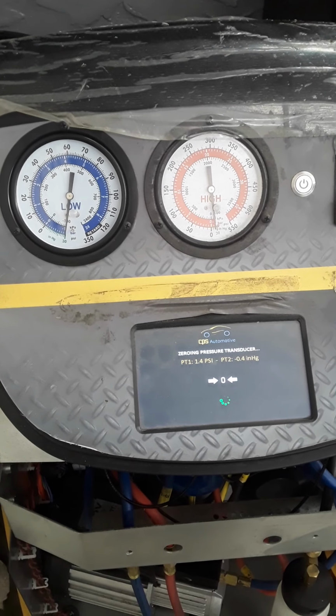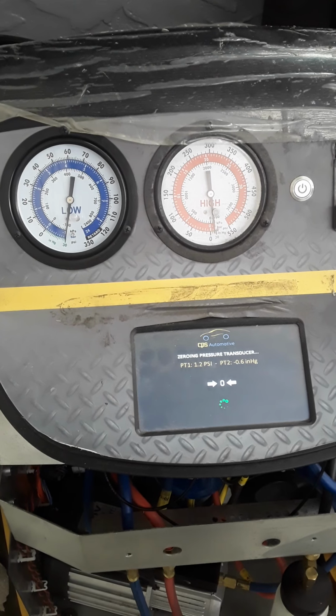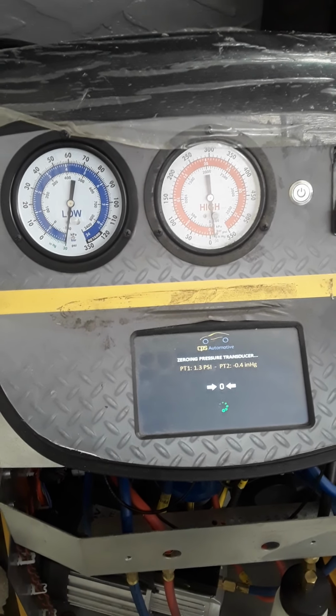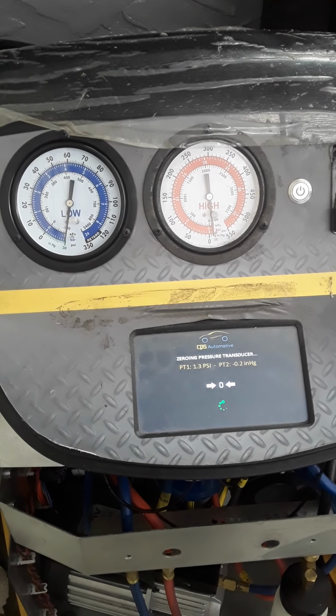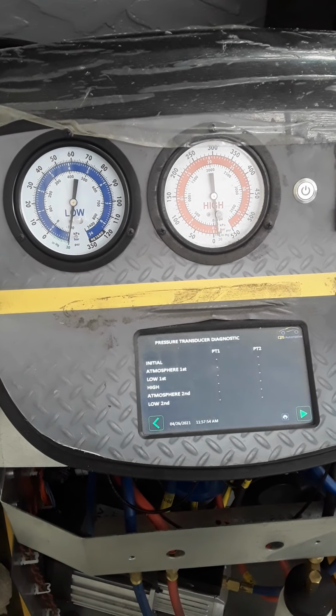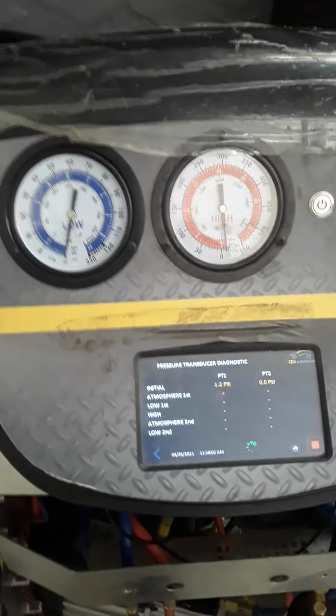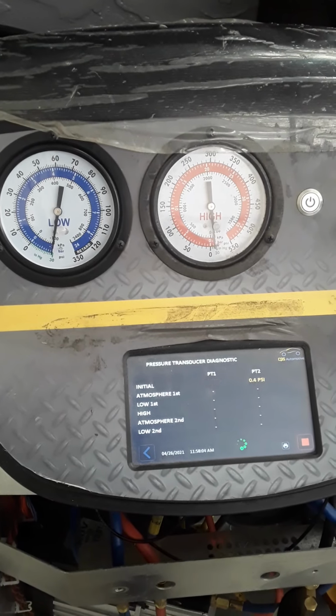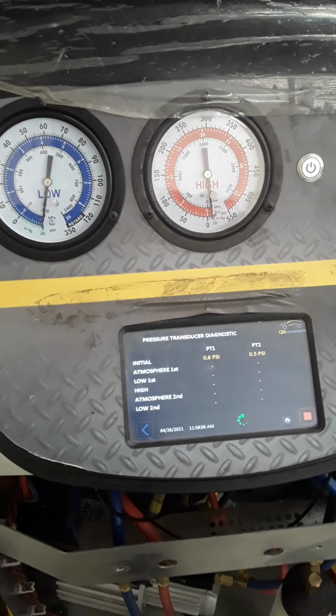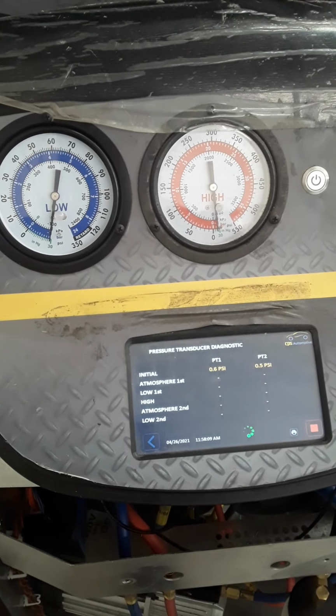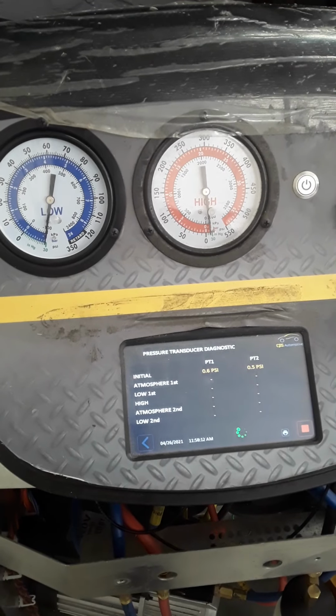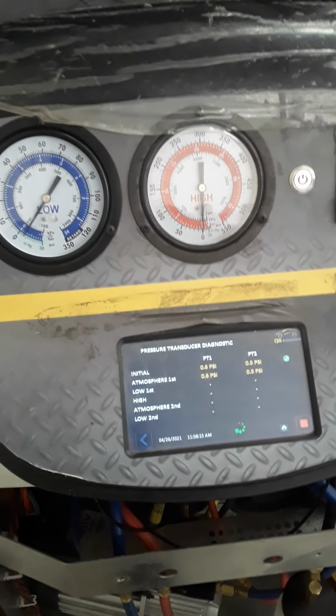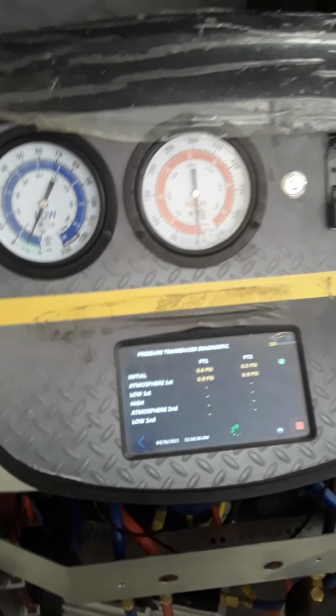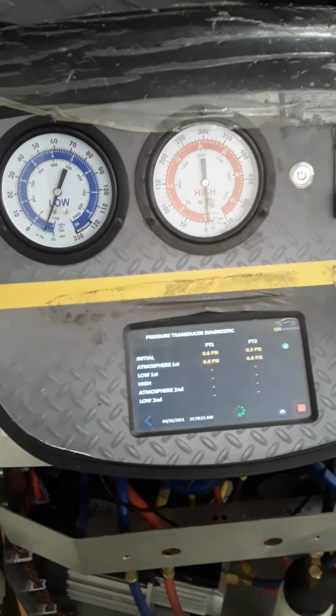Yep. Okay, what you're telling me is I had the same scenario on a machine doing what you're doing, and inside that transducer is a brass cylinder with a tiny little hole right dead in the center of it. You can hold it up to the light and see through it. I guarantee you can't see through yours, and that's why you can never get that blast pressure droppage out of there so you can calibrate it. And that makes sense to me because, like I said, we had a sealer issue. Of course, sealer messes everything up.